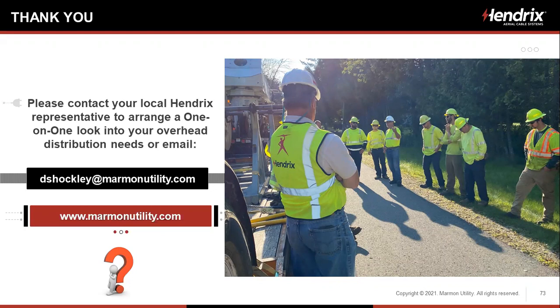However, if we had to get down in the dirt and say, what's the cost differential? I would say that when you're at 69 kV, the multiplier from bare to spacer cable might be 2.5 as much as 3.5. I would say when we get to 115 kV, it's probably in that same range, but I don't have those numbers with me, nor am I aware of those numbers. But when we do this first commercial project, which is not a trivial project, we will have a better handle on those numbers. And when we do this in a year from now, I'll be able to speak more intelligently on that.